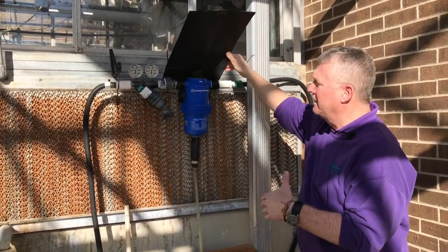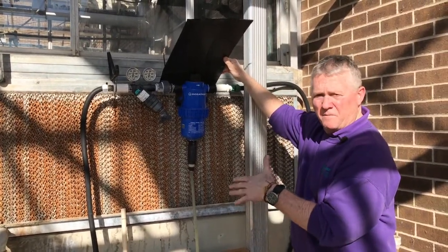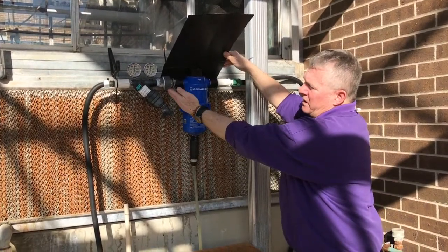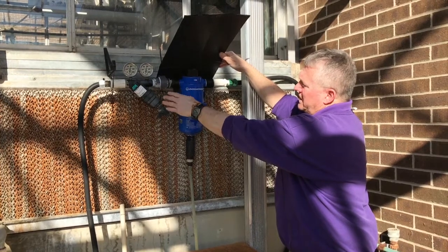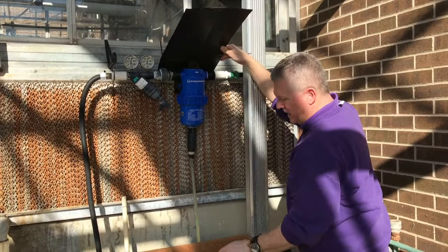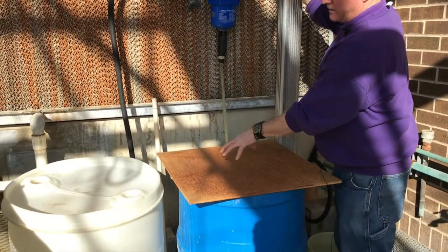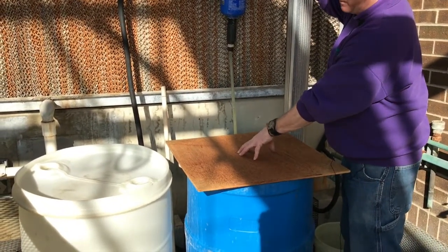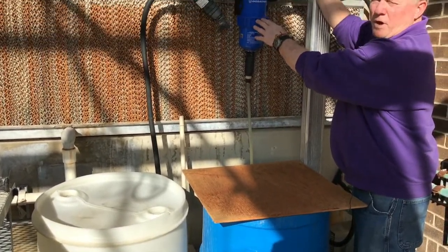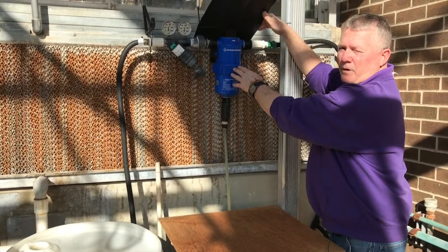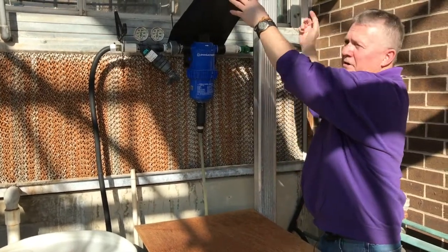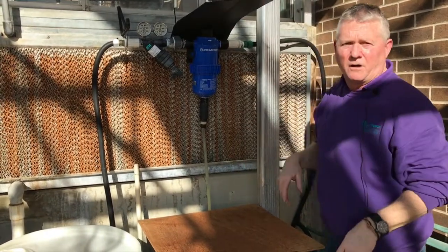So what we have here is our fertilizer injector system. This model is a Dosatron. What happens is water comes through these meters, comes through the Dosatron and through the pumping action, it siphons or draws up stock fertilizer that's located below here, and it's metered at a 1% solution. So our ratio is 1 to 100. And then it comes out through this hose here, and then it's sent down to all of the greenhouses.